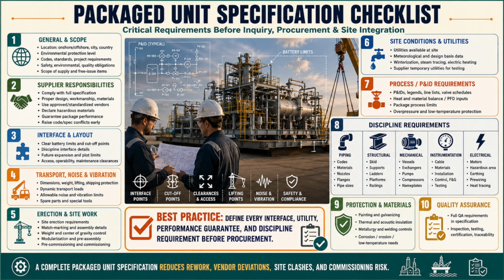The supplier must know the loads that connected equipment can tolerate, while the project piping team must know the allowable forces and moments at package interfaces. Also define cutting allowances for hookup spools, overall dimensions, weight limits, and any piping materials required for field assembly. Clarify whether the supplier provides fabricated spools, loose components, or both.